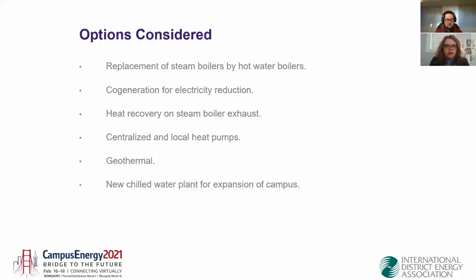So either converting the entire plant with heat pumps and having an external energy source such as geothermal, that was looked at. Of course, geothermal was looked at and considered. And again, with all the expansion that was going on campus, there was a new chilled water plant that was planned for the expansion and the addition of new buildings. The options that were kept were the heat recovery on the boiler exhaust and centralized and local heat pumps. Local heat pumps in buildings.